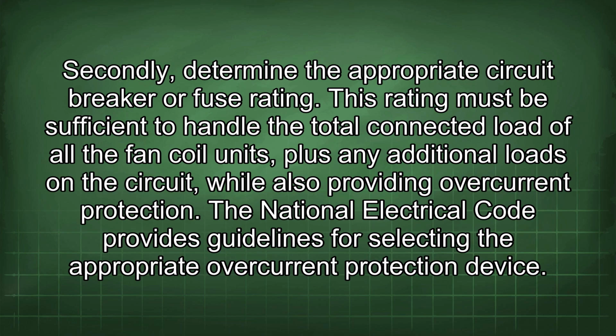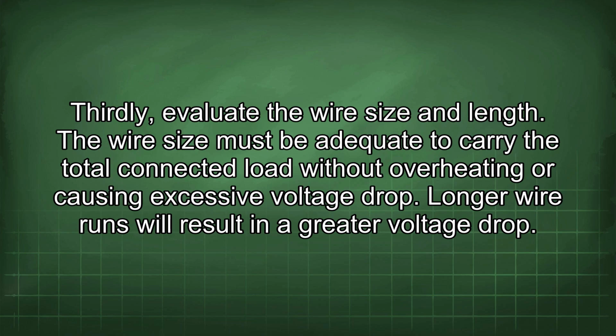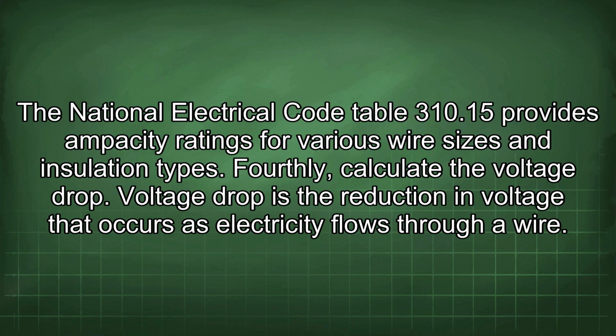Secondly, determine the appropriate circuit breaker or fuse rating. This rating must be sufficient to handle the total connected load of all the fan coil units plus any additional loads on the circuit, while also providing overcurrent protection. The National Electrical Code provides guidelines for selecting the appropriate overcurrent protection device. Thirdly, evaluate the wire size and length. The wire size must be adequate to carry the total connected load without overheating or causing excessive voltage drop. Longer wire runs will result in a greater voltage drop. The National Electrical Code Table 310.15 provides ampacity ratings for various wire sizes and insulation types.